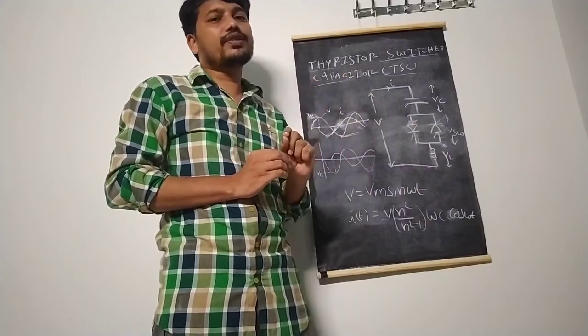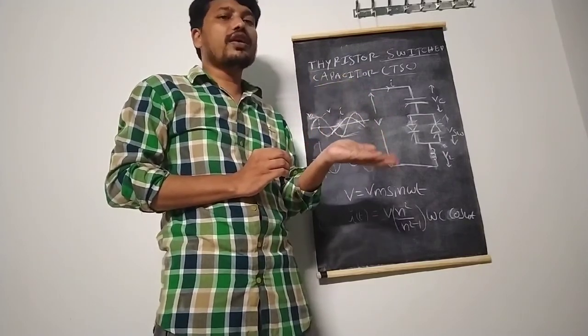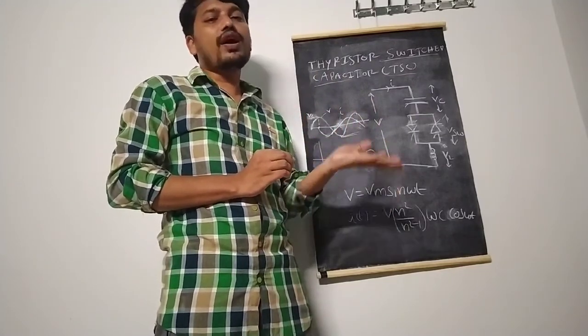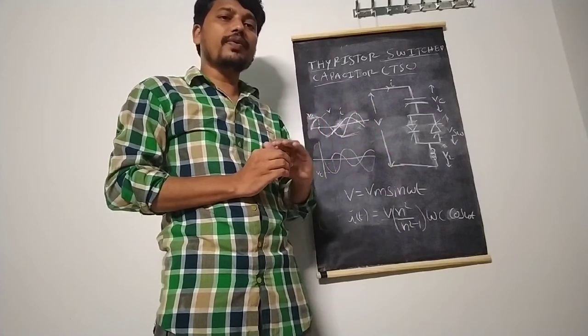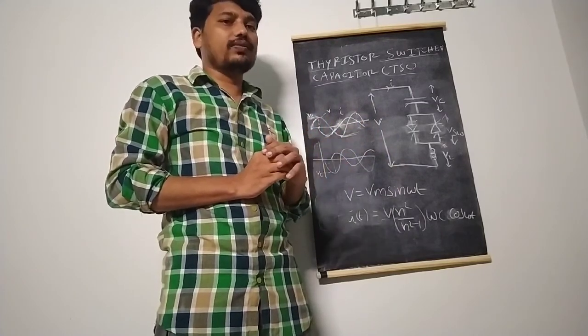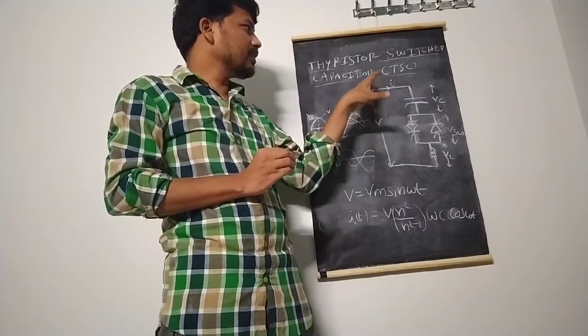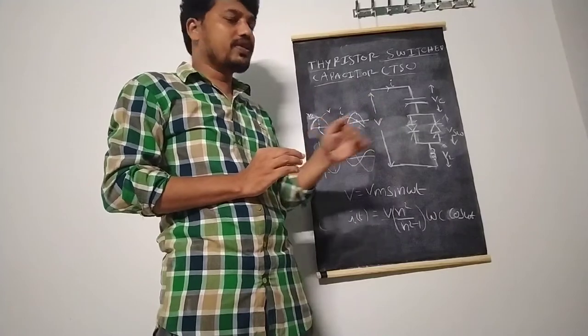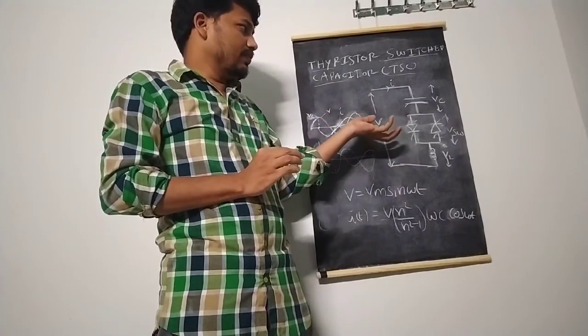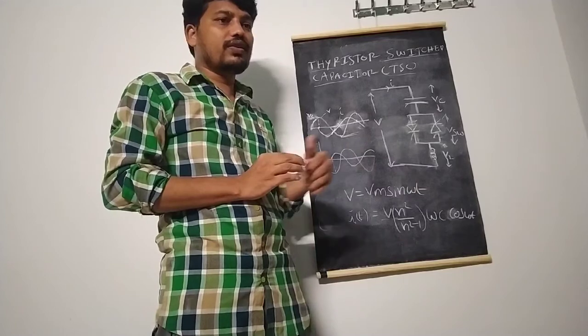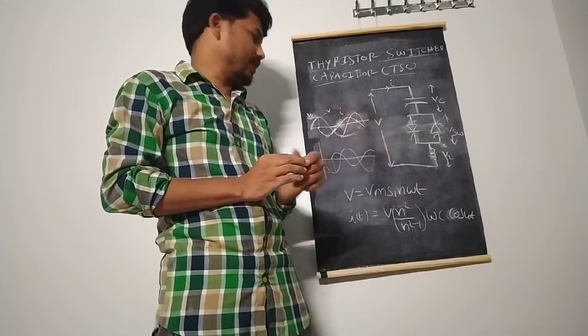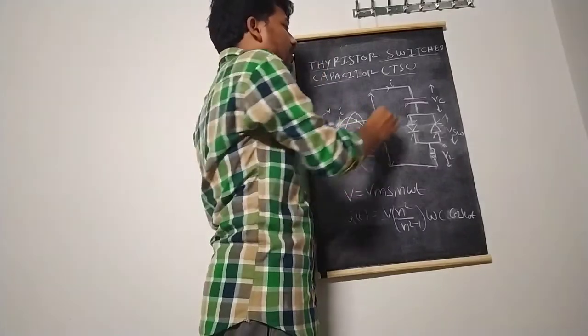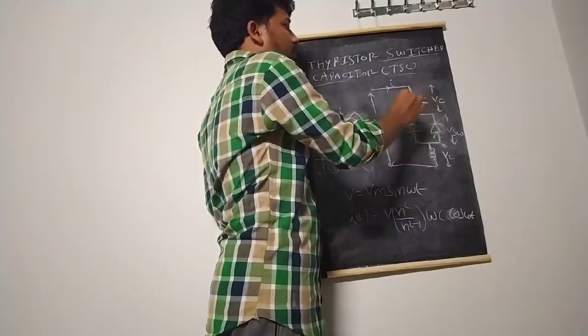The ultimate aim of this device is it generates reactive power or absorbs reactive power. In some cases, with the help of the STATCOM it can generate reactive power and absorb reactive power, as well as real power exchange is also possible in the STATCOM. But in the case of the TSC, thyristor switched capacitor, we are generating reactive power — that means we are maintaining capacitive current, generating the capacitive type of current. This is the main diagram of TSC for a particular single leg of the TSC.